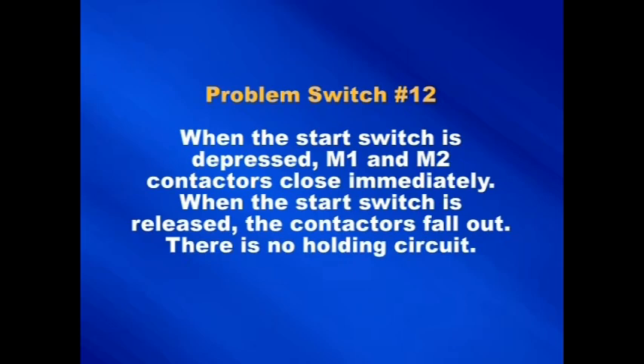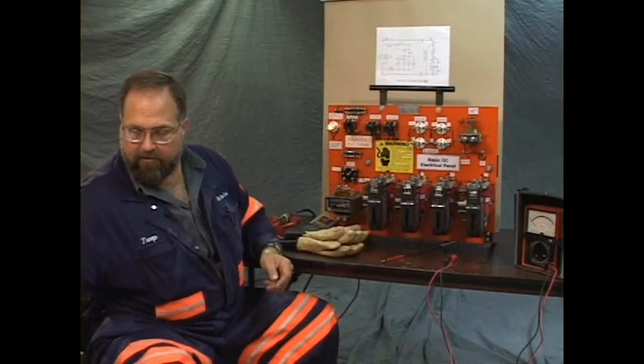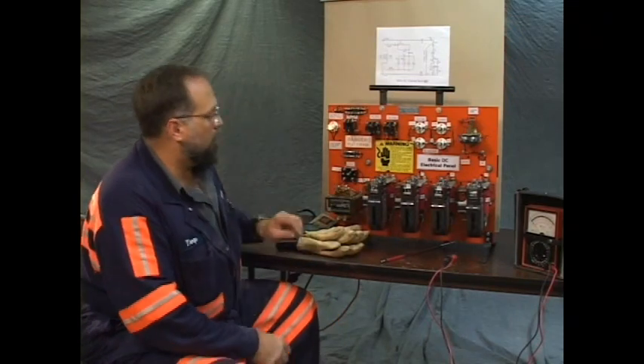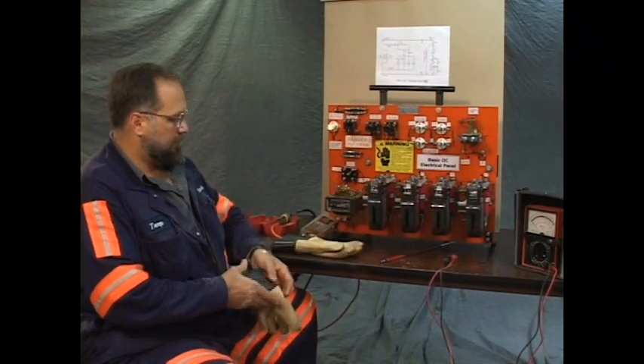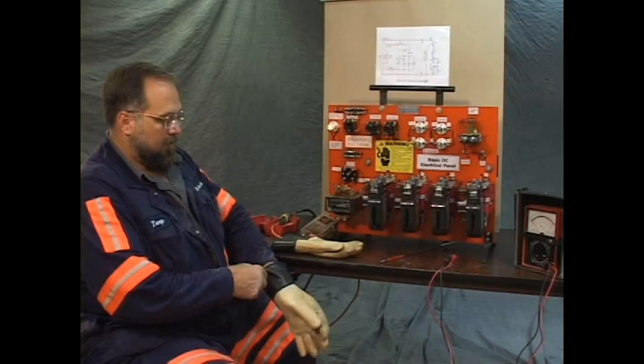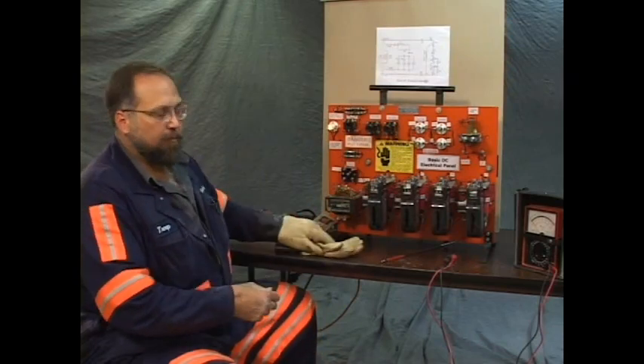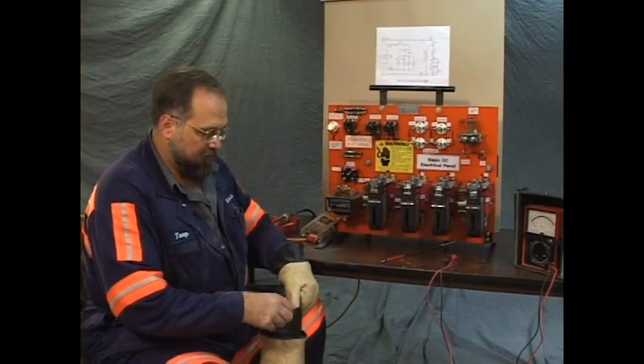When the start switch is depressed, M1 and M2 contactors close immediately. When the start switch is released, contactors fall out. There's no holding circuit. Let's show you normal operation of the panel, what should happen. And then we'll install the problem by operating a toggle.